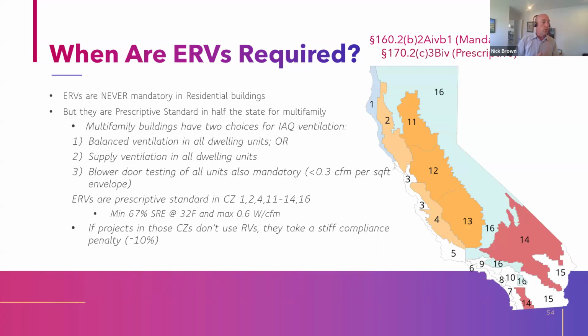So climate zones 1, 2, 4, 11 through 14, and 16 for multifamily have an ERV prescriptive standard, and they need to meet certain minimum efficiency: 67% recovery effectiveness and 0.6 watts per CFM. If you use the performance method of compliance with an ERV about that efficient, you'll stay pace with the code in those climate zones. If you use a best-in-class ERV, you'll open up a nice compliance margin. And if you install one in a climate zone that doesn't have the ERV prescriptive standard, you'll open up a nice compliance margin as well. Conversely, if you try to build a multifamily building in those climate zones without ERVs, you're going to take a stiff compliance penalty that you have to make up for elsewhere.